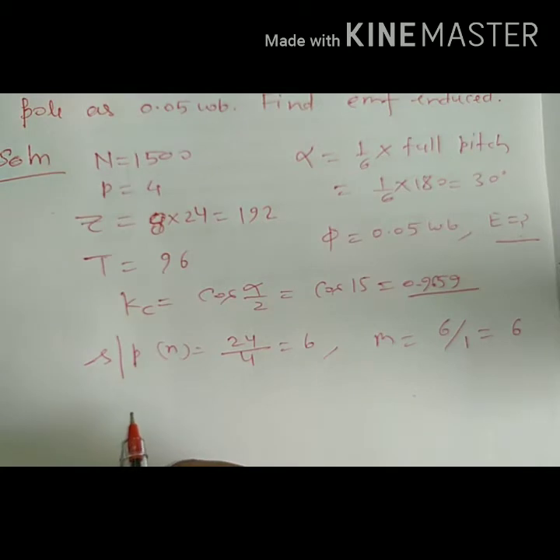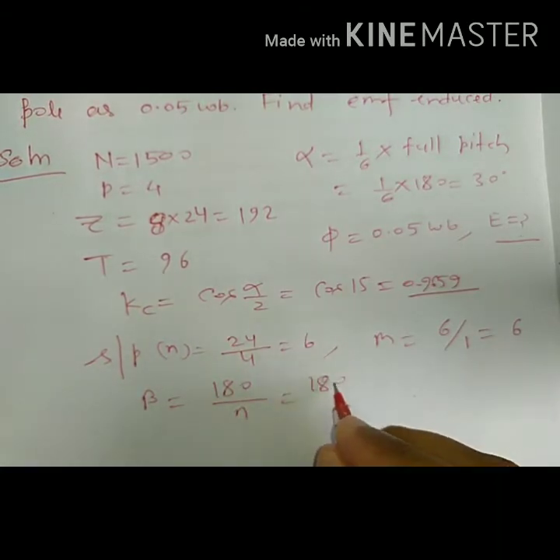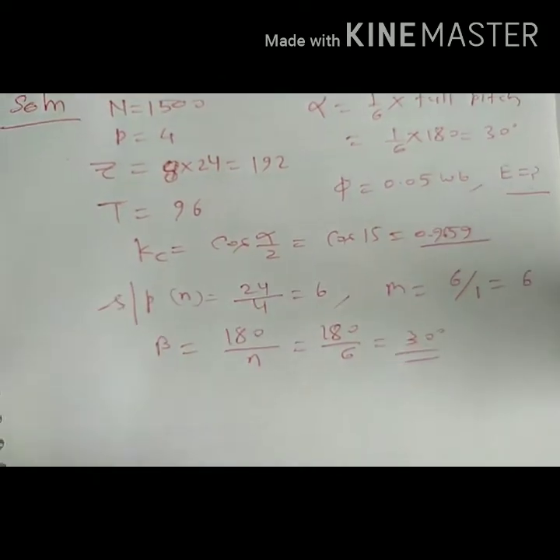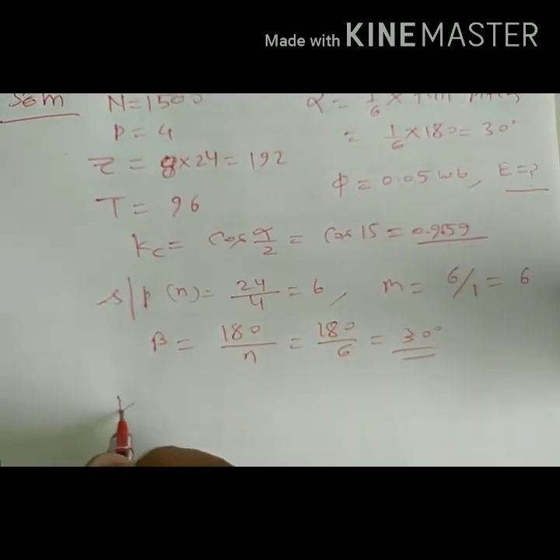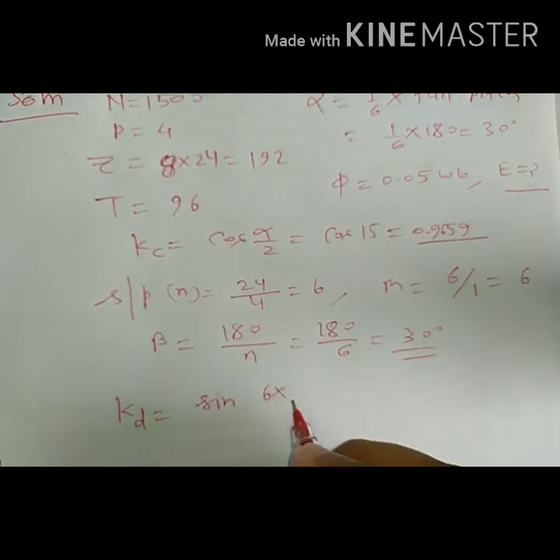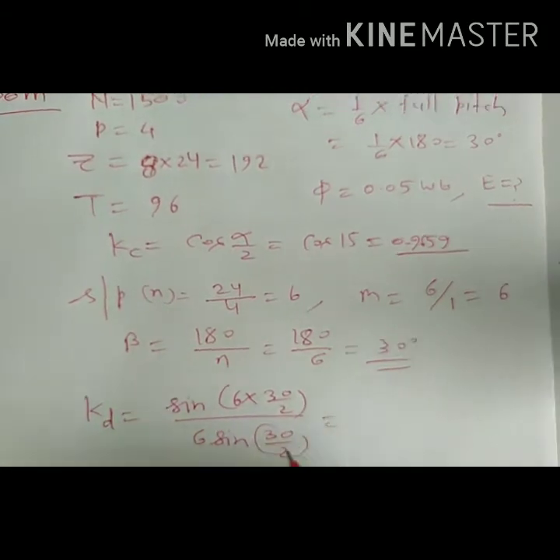Slot angle beta will be 180 divided by slots per pole, that is 180 by 6, which is 30 degrees. Now find the distribution factor Kd: sine of (m·beta/2) — where m is 6 and beta/2 is 15 degrees — divided by m times sine(beta/2), which is sine(15 degrees).